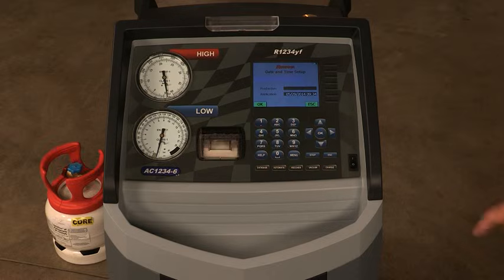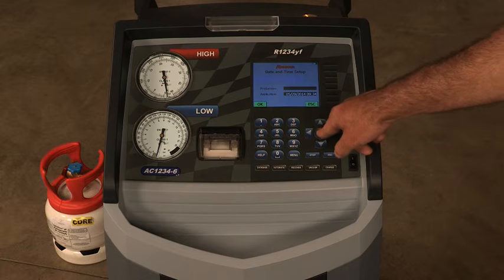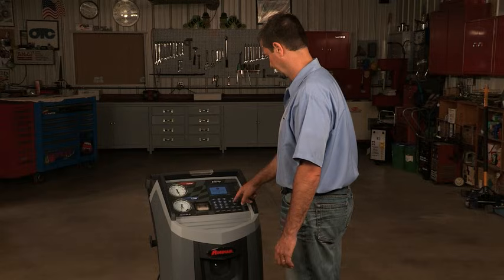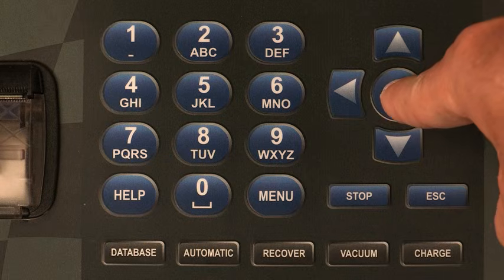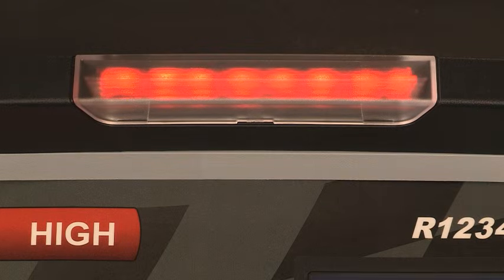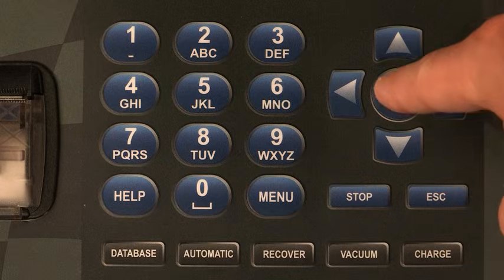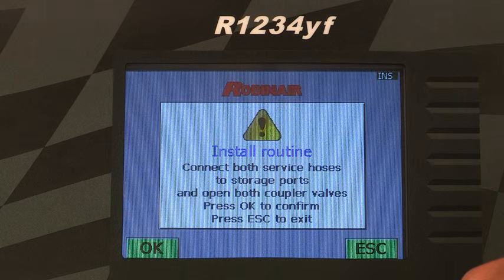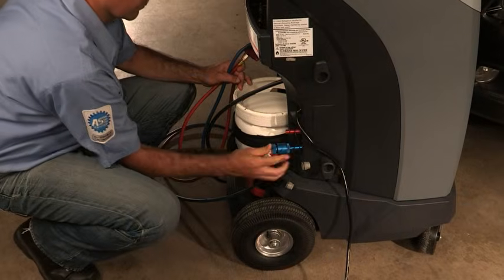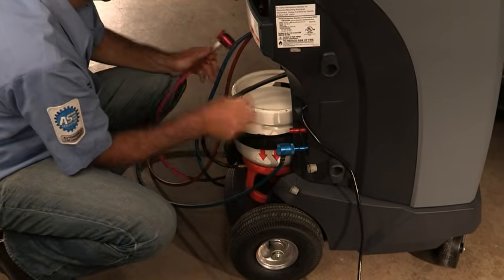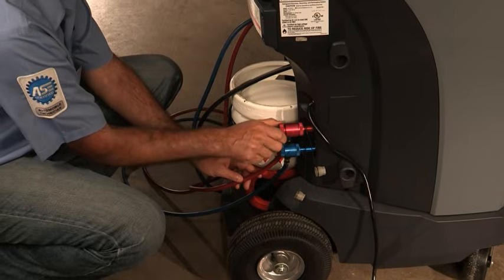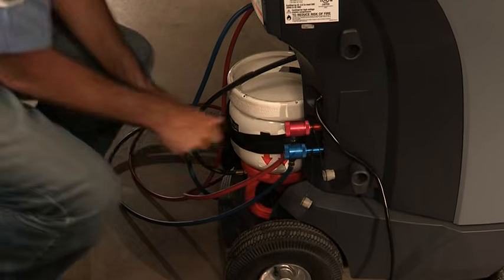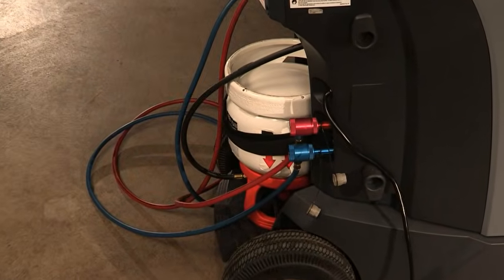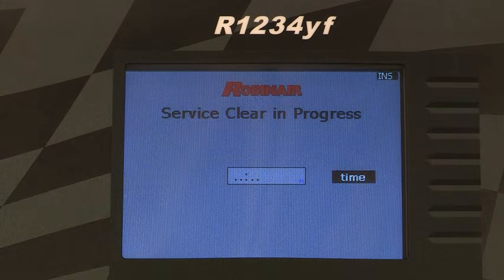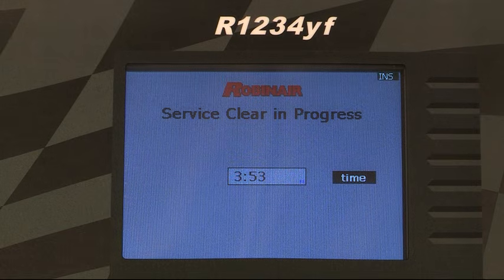The machine is programmed at the factory for the local time zone using a 24-hour clock and date. Use the left and right arrow keys to modify the minutes displayed. Use the up and down arrow keys to modify the hours displayed. Press OK to accept the date and time. At this point, the machine clears its internal plumbing before proceeding with the setup. When prompted, connect the service hoses from the machine to their storage ports. Open the service couplers. The machine performs an internal clearing of its plumbing.